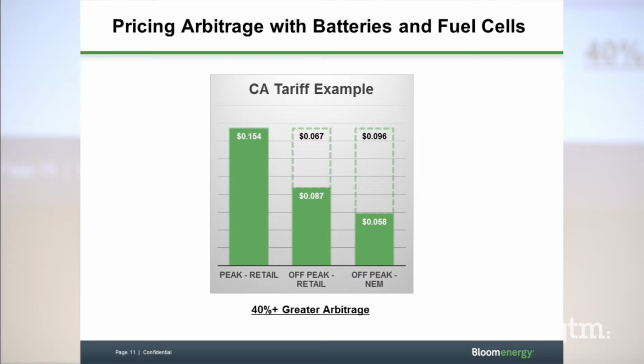Now, some of you may ask, why couldn't you do this with solar? We get that question all the time, and we're deployed jointly with solar in a lot of places. The reason you can't is that for customers like ours—multi-100 kilowatt customers, 200 kilowatts and above—they don't have the roof space, or the ratio given the capacity factor of solar, to actually have extra power. Plus, solar is producing power during peak times, so you'd rather discharge it during peak rather than put it in storage. Typically solar only impacts 10 to 15% of a load curve for the commercial customers we're serving, versus us impacting 60 to 80% of their total load curve. That's a big difference in terms of the technology synergies we have, as well as the amount of load curve we serve for the customer.